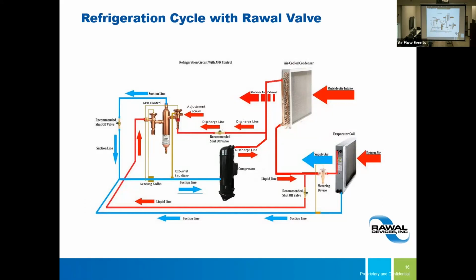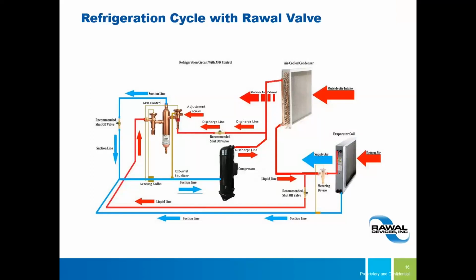And you've put these on a few units, yeah. Lots of them. So far, so good. So you use a thermostat that has a dehumidification setting that then keeps the call for cooling going. We'll have a primary temperature and secondary humidity, and then as long as you force the unit to keep running, and like I like to use it, say you've got 2 or 3 stages of cooling, you just put the Rawal valve on the first stage, and then you get all that additional modulation through the system. Or if you can only get a unit that size with 2 stages, all of a sudden you get 60% more flexibility just putting it on one stage. We have put it on both stages, but usually just the first stage works really good, especially for those cool humid days. That's where meeting spaces and stuff, conference rooms, rooms like this. Yep. Yeah, like 70 and raining days kind of stuff.